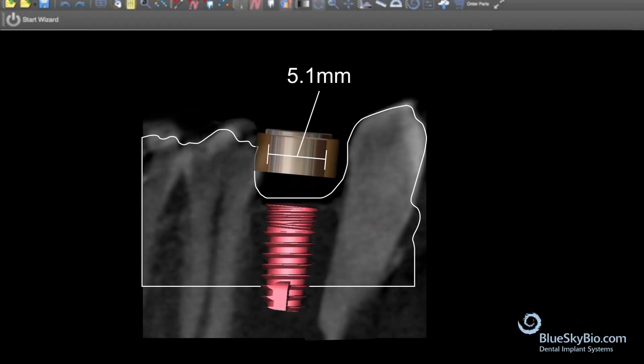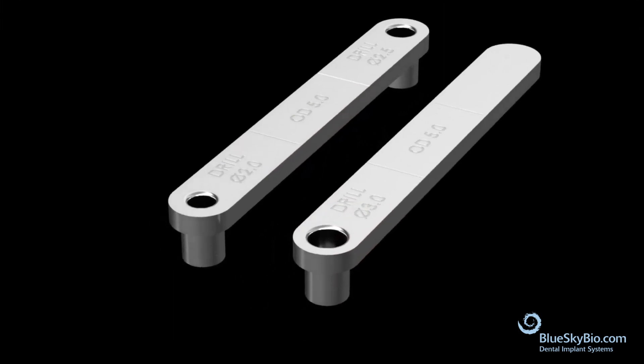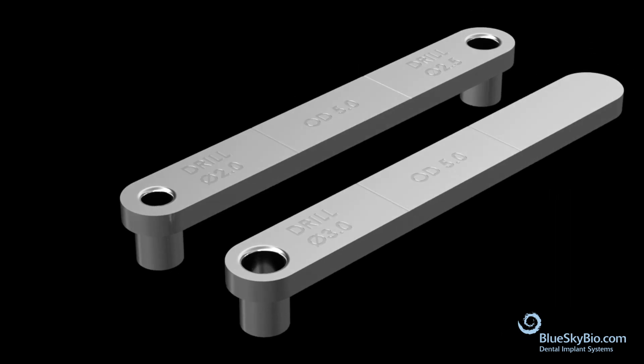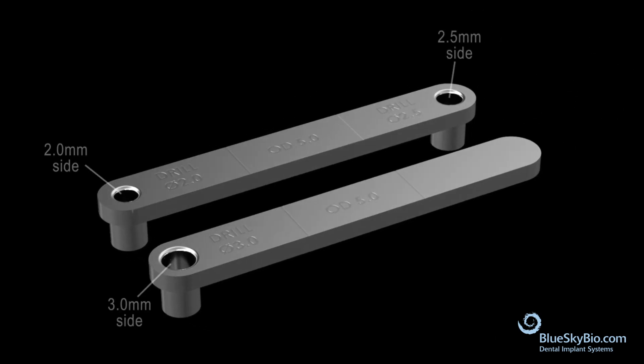For implants of 3.0 or 3.5 diameters, using Blue Sky Plan, generate an implant guide using a standard guide tube with an inner diameter of 5.1 millimeters. The tube will match the key with an OD of 5.0. Use the keys with the smaller outside diameter tube. These inner diameters are labeled near each hole.